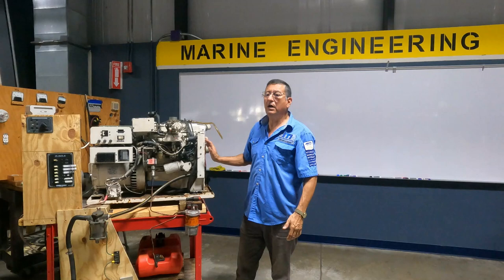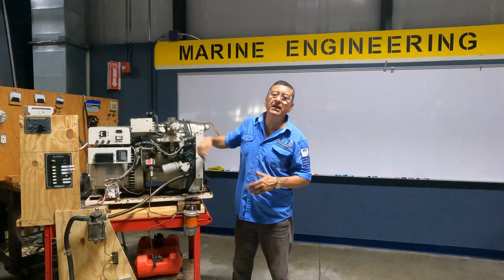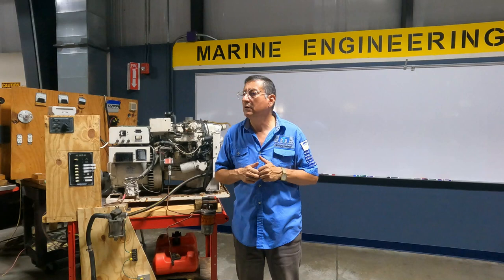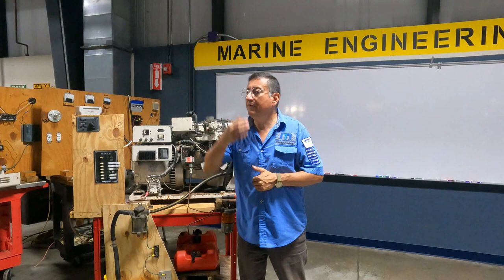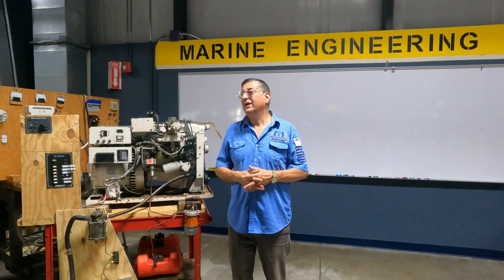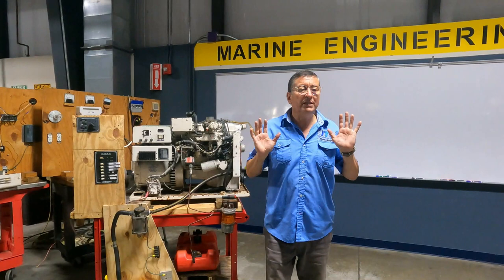If I have low frequency, don't touch the alternator, you have problems in the engine and the engine is running with low RPMs. Reasons for low RPMs in the engine: bad fuel. What happens if the air filter is clogged? You can't run well. Yeah, it is a problem with fuel or air filter. That's it. The frequency is supposed to be stable all the time.